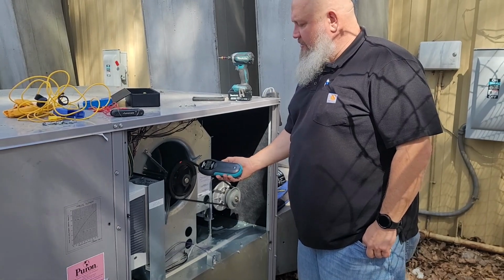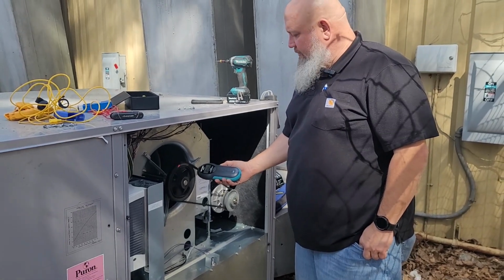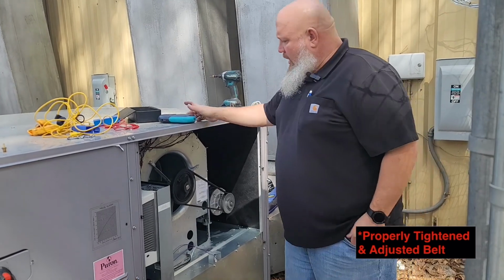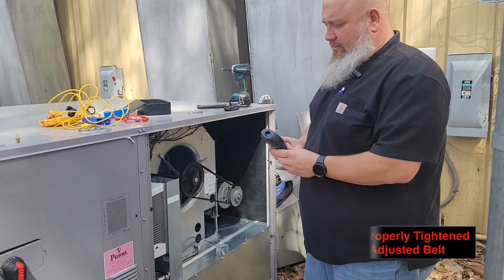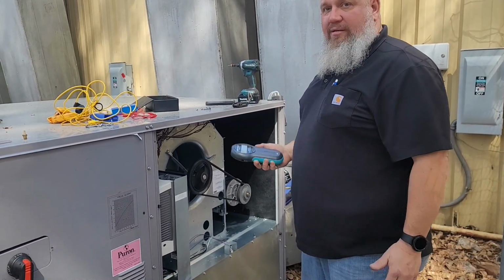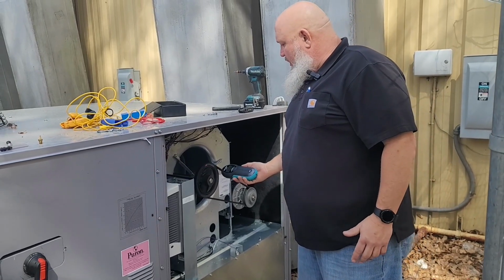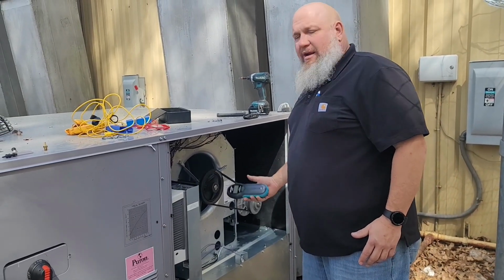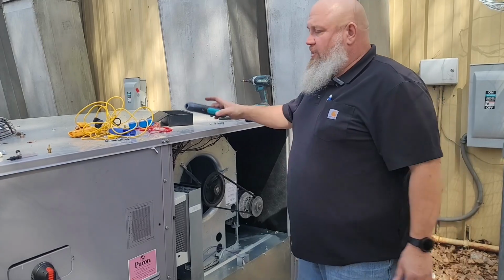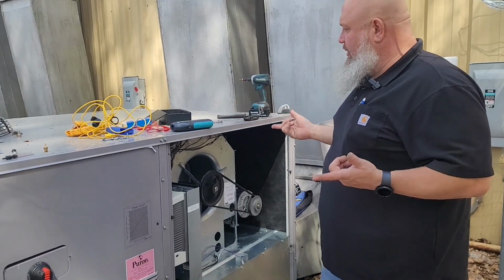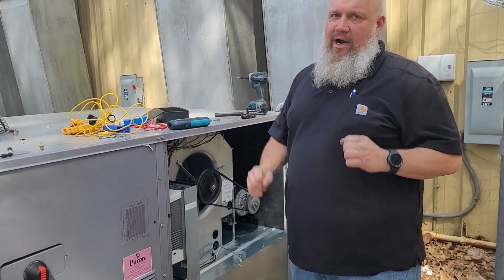And we're running 856 RPMs right now. Tell me what you just did. We tightened the belt and adjusted it, just a little bit. And now we're running 915 RPM. So we need to recheck our static pressure and look at the chart again to make sure where we're at. Yes.